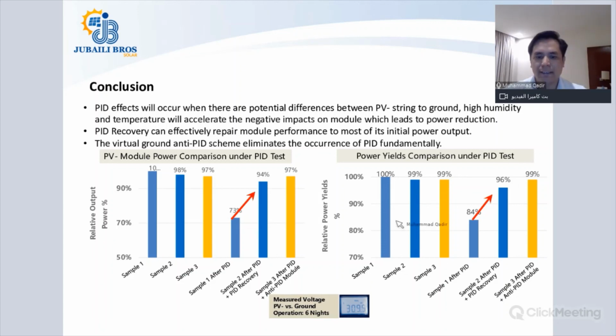And looking at the second graph, this is showing you the negative impact on the power yield of the inverter. Initially, in the 3 samples, the inverter was giving you very high output, and after having been exposed to a PID environment, the production of the PV plant decreased to 84%. After having used the NT-PID and the PID recovery function of the inverter, it increased to 96%, and having used the NT-PID module, which is a separate type of solution, the yield has increased to 99%.